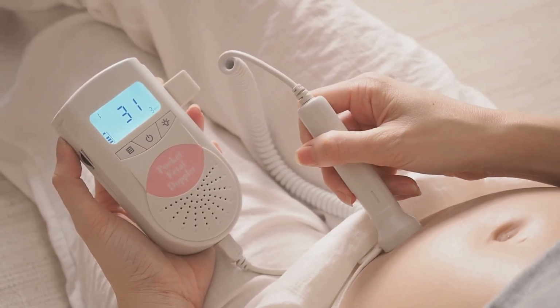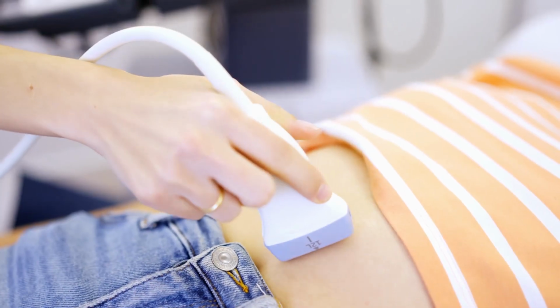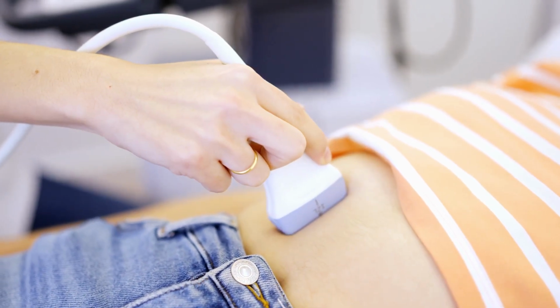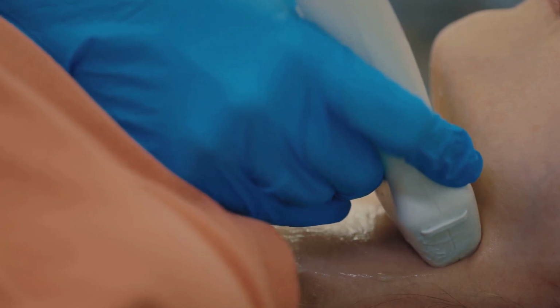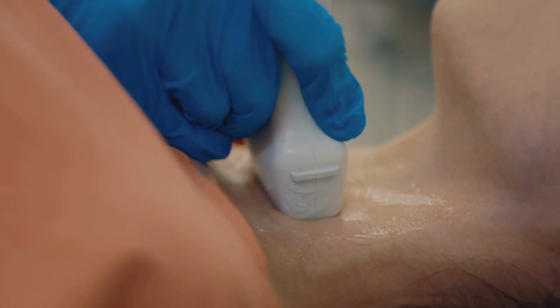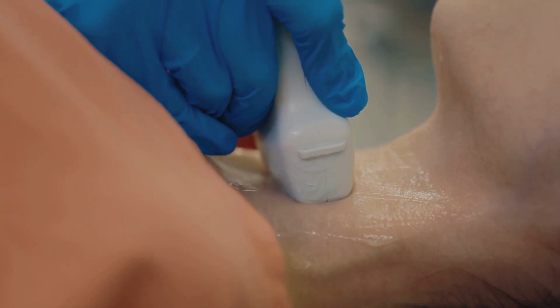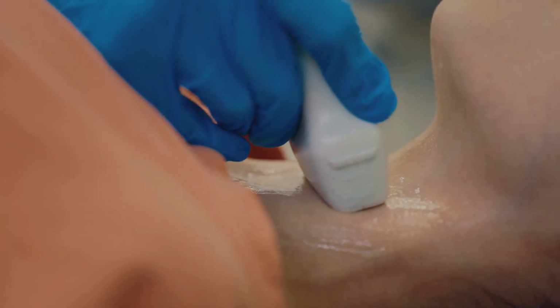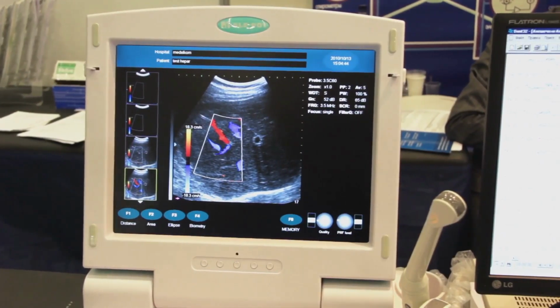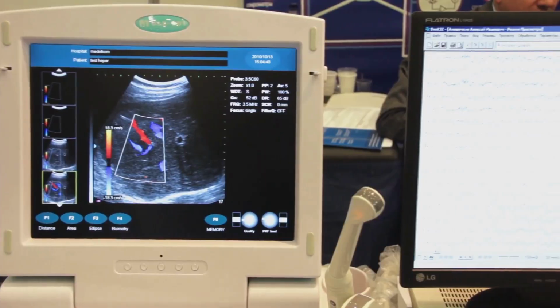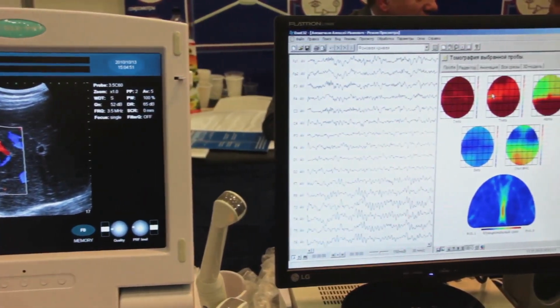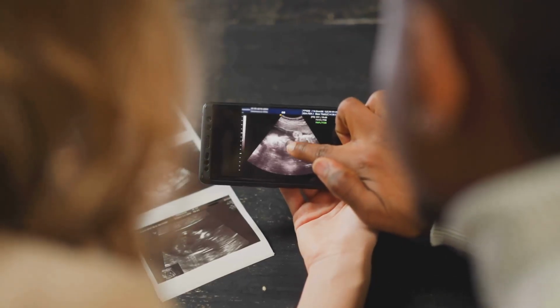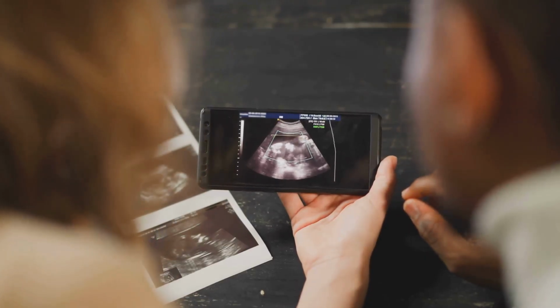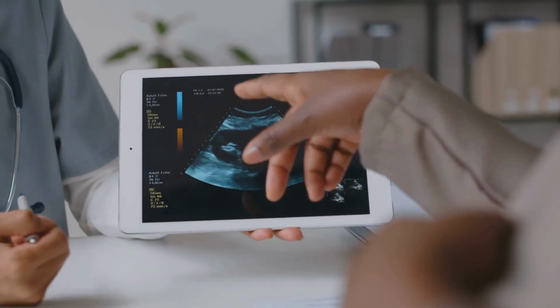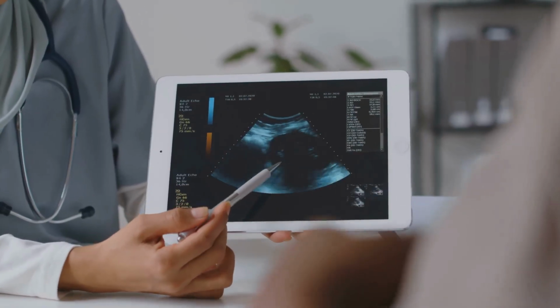Most home systems rely on ultrasound because ultrasound hardware can fit inside a compact probe powered by a rechargeable battery. Instead of a room-sized MRI machine with a massive magnet and a sliding patient bed, a home setup uses a palm-sized probe that plugs into a phone or tablet through a cable or wireless connection. Inside that probe, rows of piezoelectric crystals expand and contract when electrical pulses travel across a small circuit board. Those vibrations send high-frequency sound waves into tissue beneath the skin. The returning echoes strike the crystal array, generate electrical signals that travel back through wires, and feed data into a processor chip that reconstructs a two-dimensional image on the glass display.